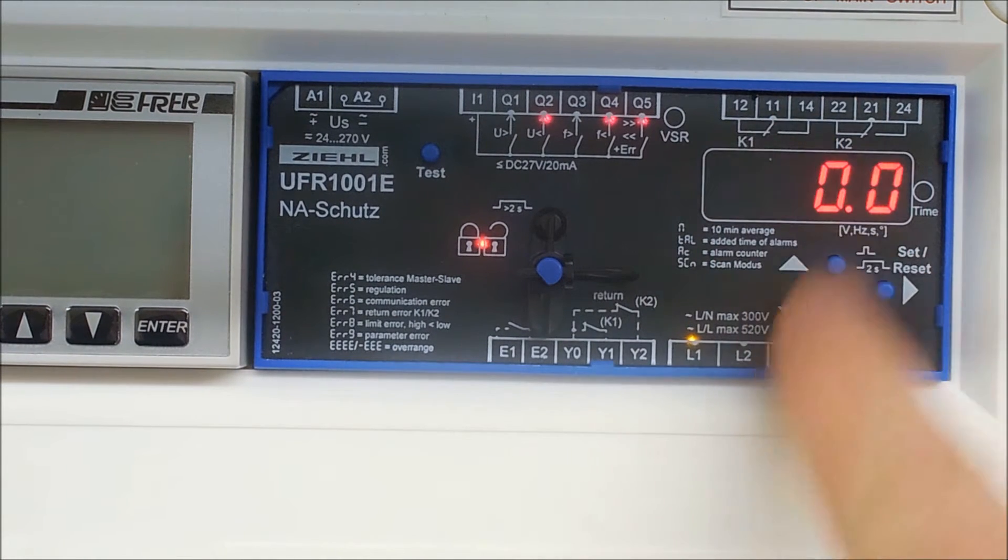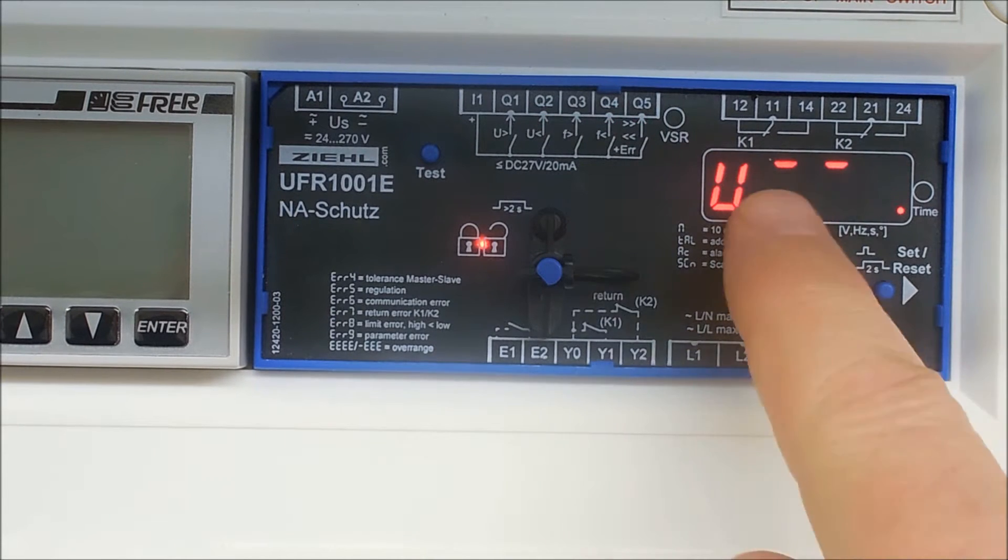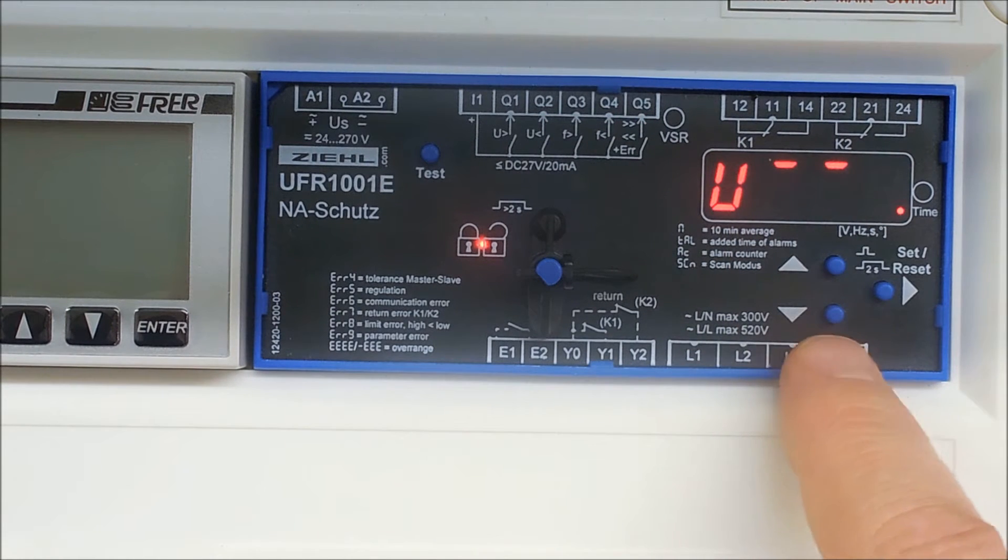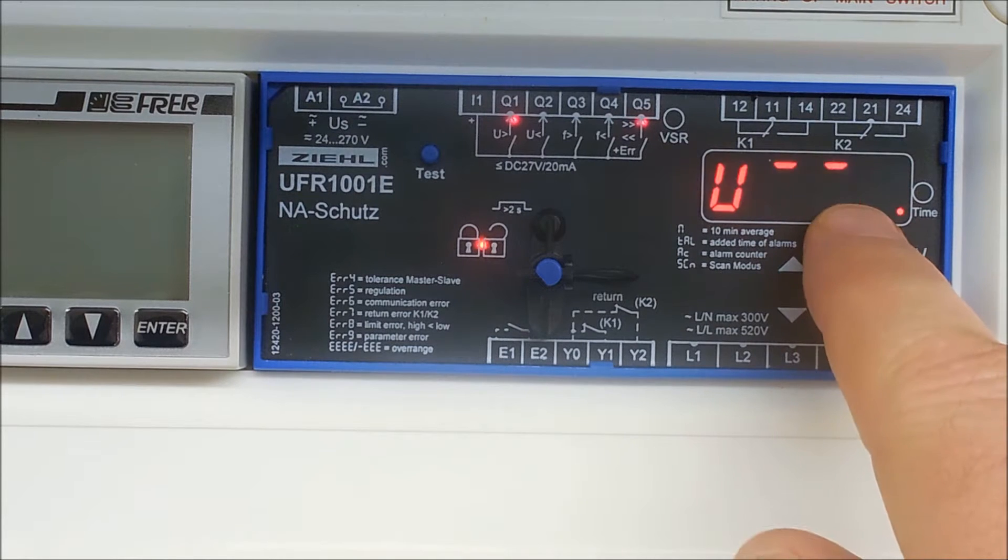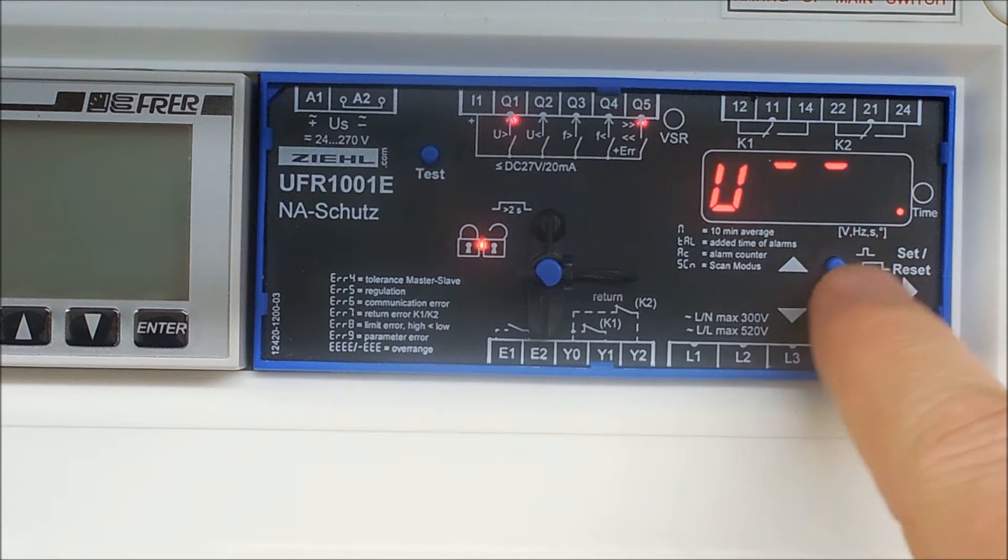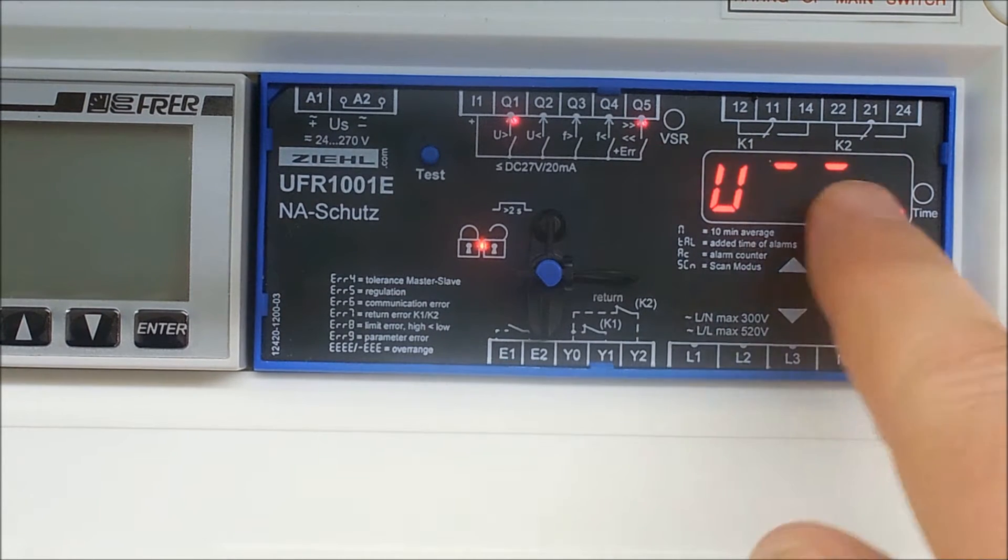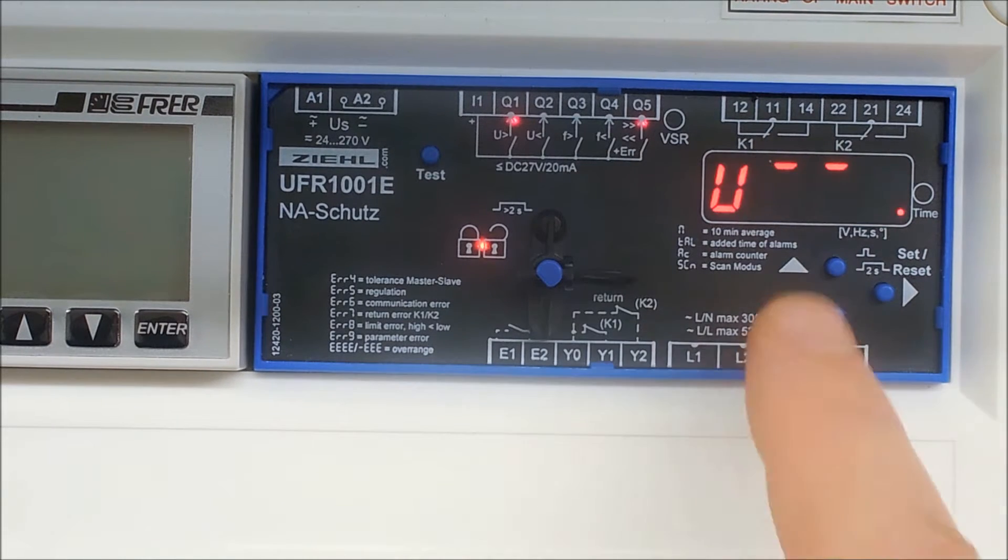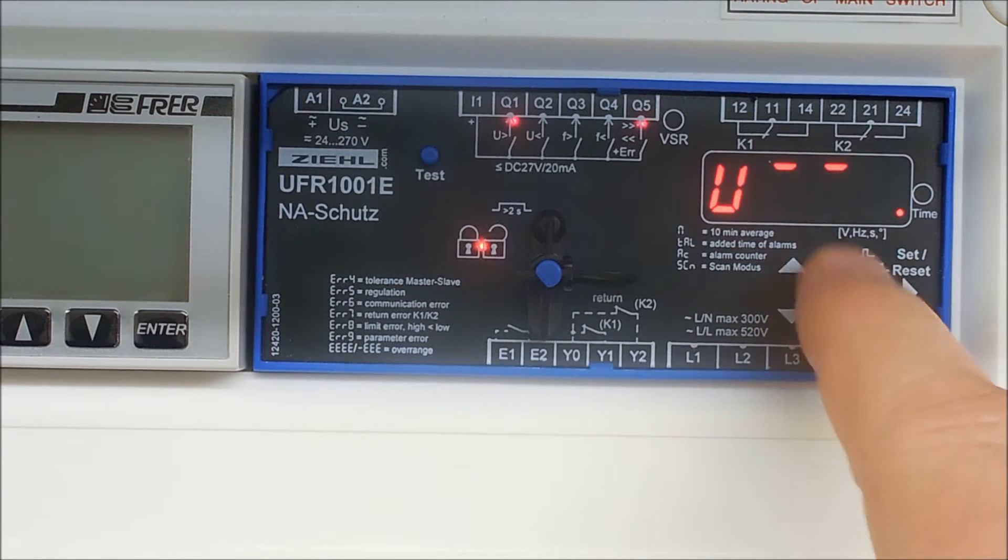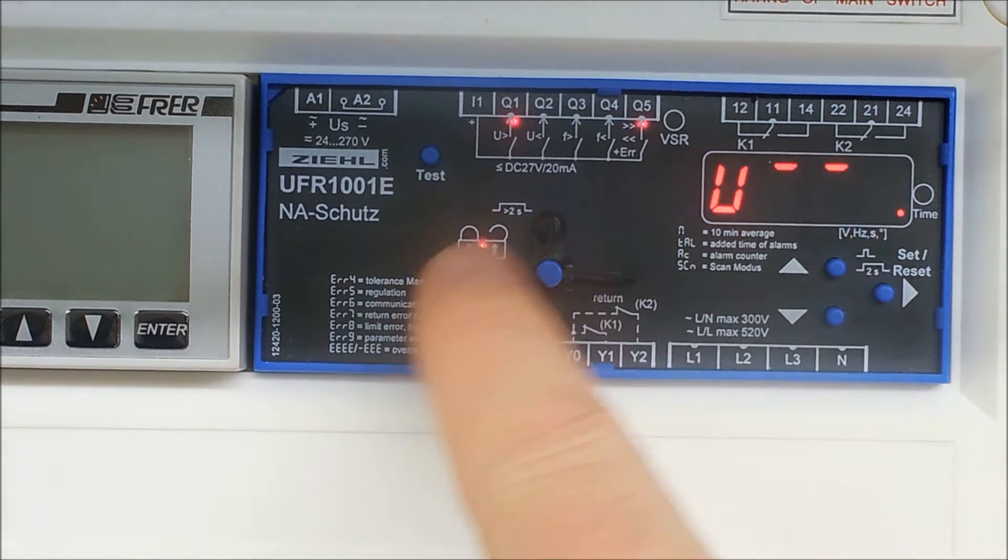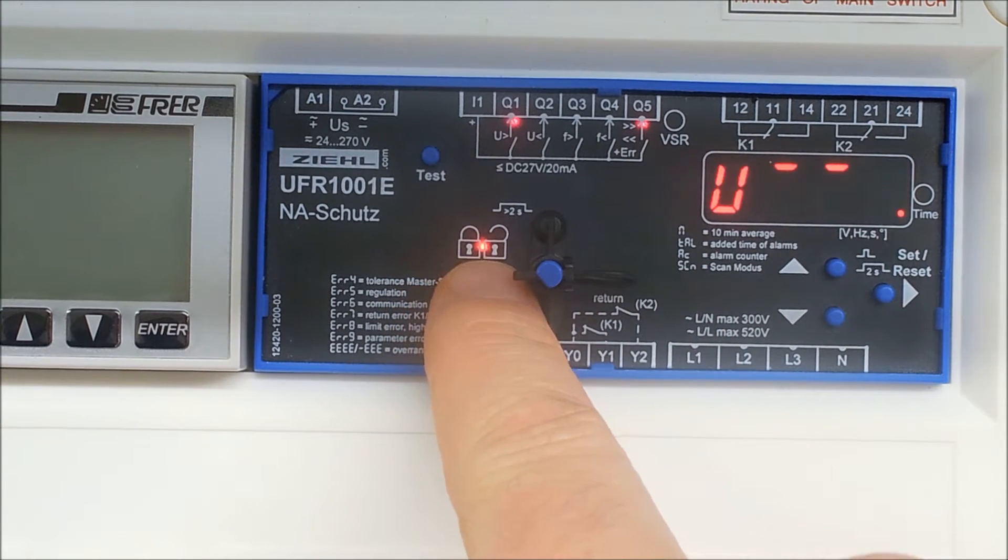If you press the down arrow key you come to the first value in the list which is over voltage second level. If you press the right arrow you can see this is an active monitored value. If you press the right arrow again you can see the value is 476. If you now try to change this value by pressing the up or down key it will come up with LOC and at the same time this LED here will flash.